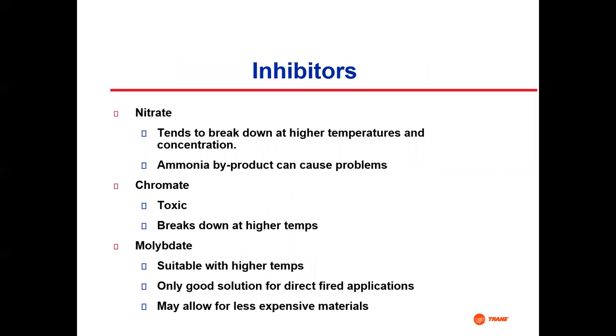Okay, so this lithium bromide, and it should say this, I'm going to modify this slide, I was thinking about it, but I ran out of time. This has to do with corrosion, because salts are corrosive. So lithium bromide is very corrosive. So in order to avoid corrosion problems, we put inhibitors in. Well, of course, then the inhibitors can cause problems. So you have to worry about having your chemicals right in order to prevent corrosion in the machine.